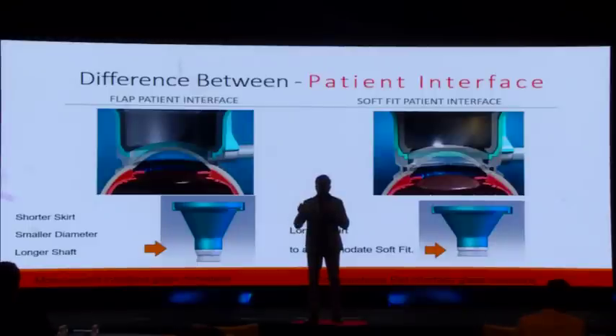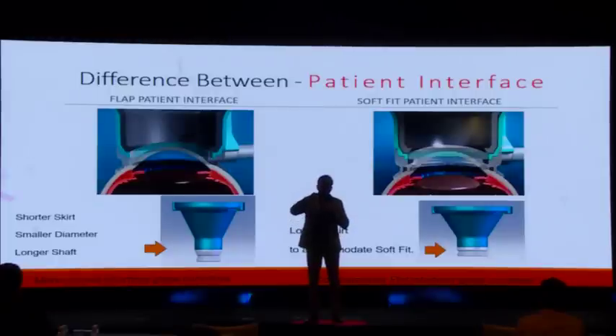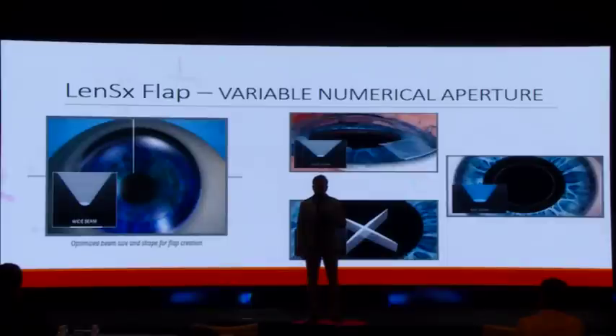This is achieved through the patient interface — the key to the LensX flap. The skirt is shorter, the diameter is smaller, and the shaft is slightly longer; the cone interface is slightly steeper. This allows the PI to dive deep inside the eye and fit tightly when the flap is being made, as compared to a soft-fit patient interface. The proprietary variable numerical aperture is also important: for cataract procedures the laser uses wide, narrow, and mid beams for different steps, while for the flap procedure only the wide beam is used.